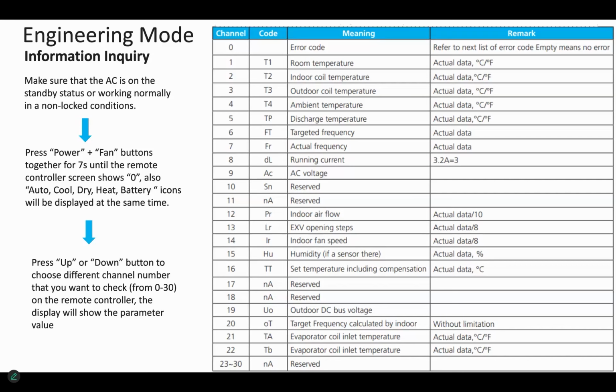LR, which is number 13, that's your EEV or EXV opening steps. That number is multiplied by 8. 14 and 15: 14 is your indoor fan speed in RPM. 15 is humidity, the actual humidity sensor reading. That is supposed to be there. That should be there.